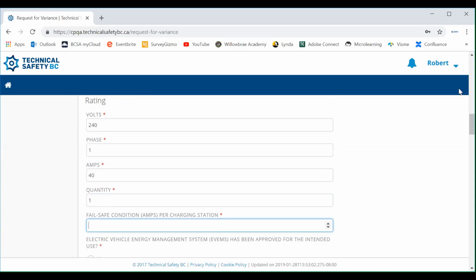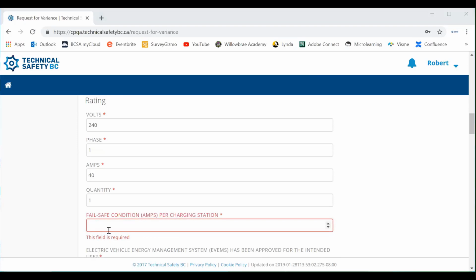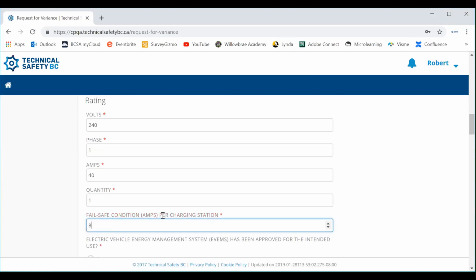In some instances, some units are going to have a fail-safe value to them. We're going to include a fail-safe here, not necessarily matching manufacturer specs, but just to show you how, when we present the demand calculation later, you're going to want to factor in fail-safe. So in this case, we're going to give a fail-safe value of 8 amps.